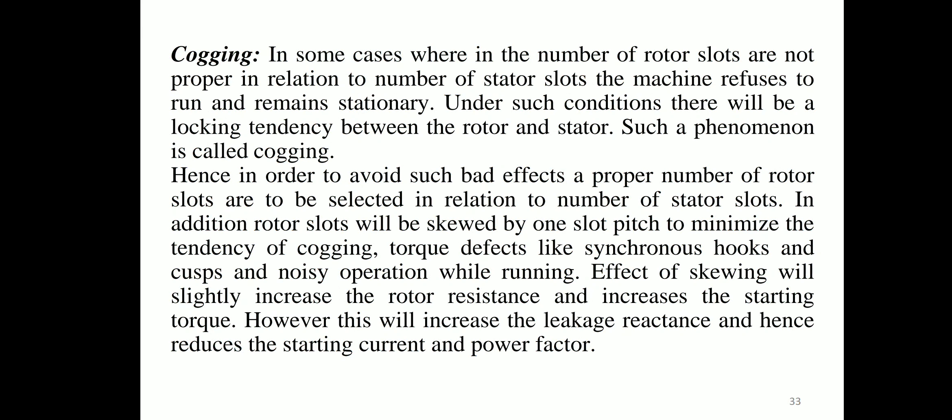Cogging occurs when the number of rotor slots are not proper in relation to stator slots — the machine refuses to run and remains stationary due to a locking tendency between rotor and stator. To avoid such effects, a proper number of rotor slots must be selected. Additionally, rotor slots are skewed by one slot pitch to minimize cogging, torque defects like synchronous hooks and cusps, and noisy operation.